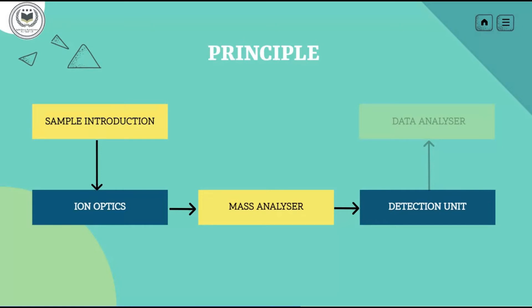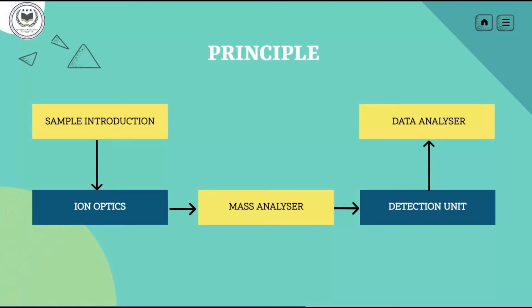At last, comes the data analyzer. ICP-MS accurately determines how much of a specific element is in the material analyzed. In a typical quantitative analysis, the concentration of each element is determined by comparing the counts measured for a selected isotope to an external calibration curve that was generated for that element.